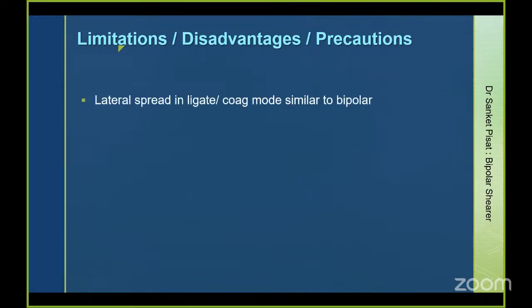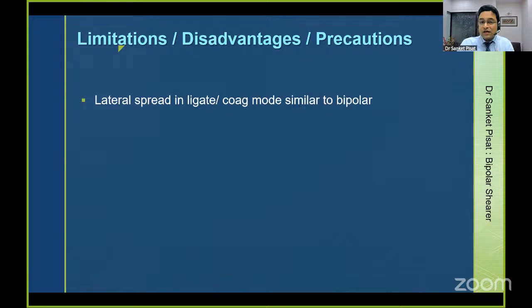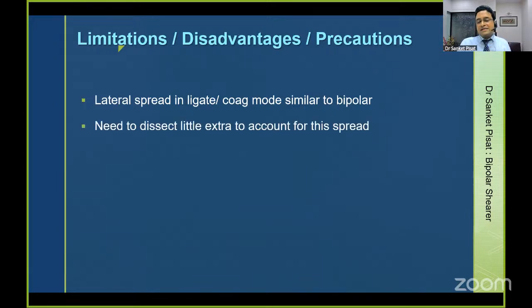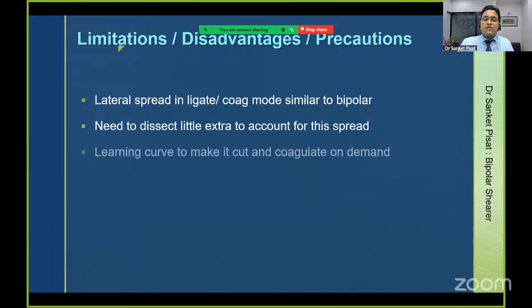What are the limitations? The lateral spread in ligate mode is similar to bipolar, so you have to consider that you're using a bipolar only. Need to dissect a little extra to account for this spread. So you cannot dissect as much as you dissect for a ligature. You have to dissect a little bit more to account for the lateral spread.